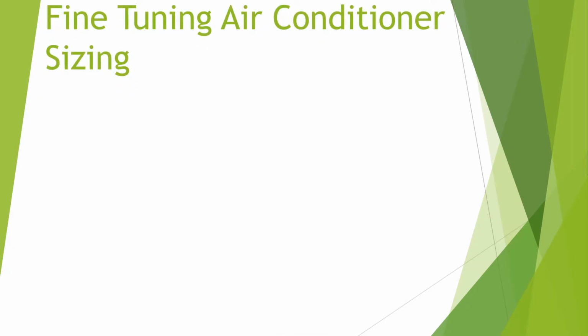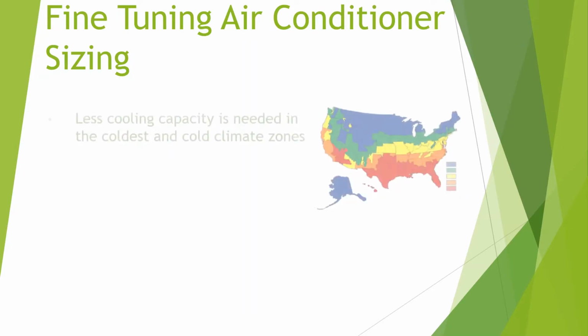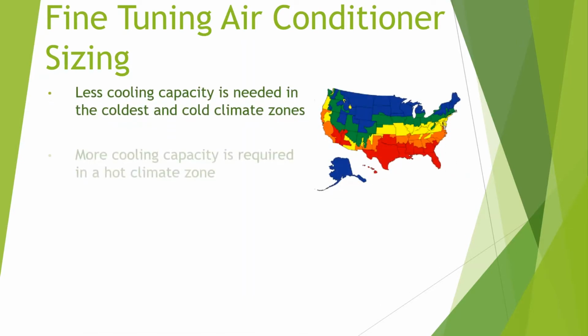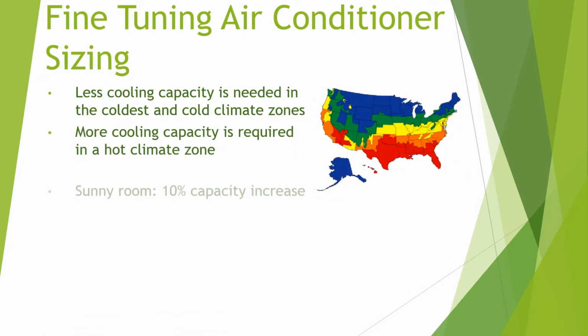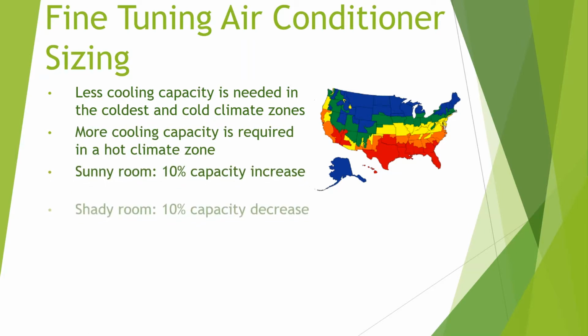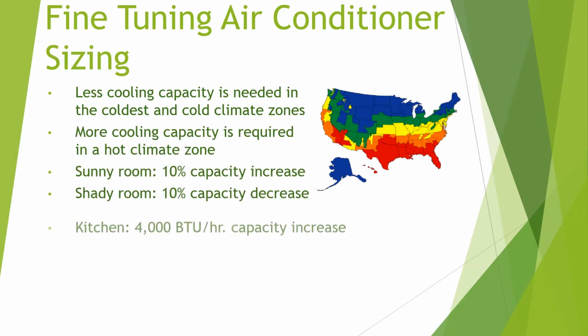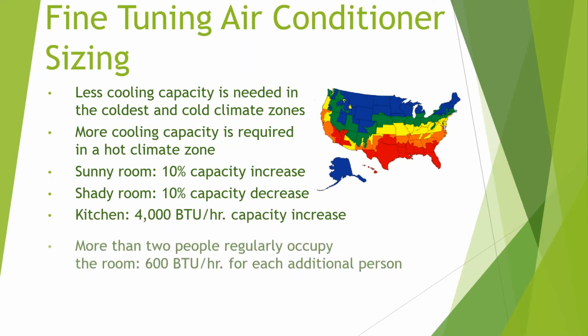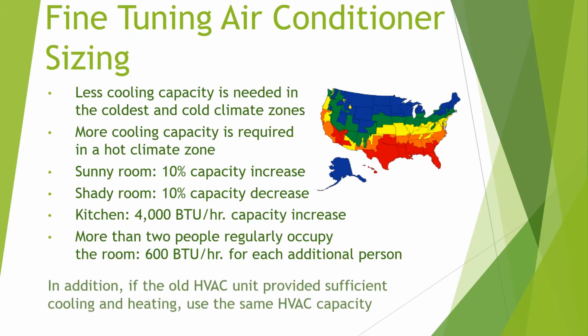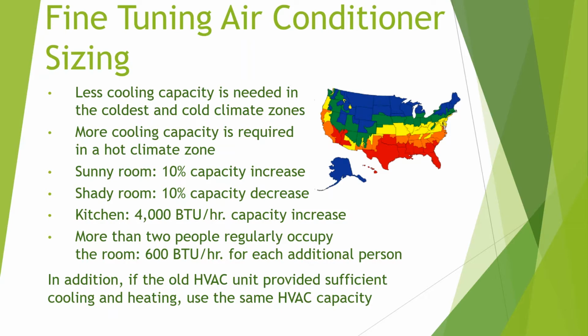You should also take into account other, more subtle things about the area where you live. For example, less cooling capacity is needed in the coldest and cold climate zones, and more cooling capacity is required in a hot climate zone. Sunny rooms require a 10% capacity increase, while shady rooms require a 10% capacity decrease. Kitchens require a 4,000 BTU per hour capacity increase, and more than 2 people regularly occupying the room require a 600 BTU per hour increase for each additional person. In addition, if the old HVAC unit provided sufficient cooling and heating, use the same HVAC capacity.